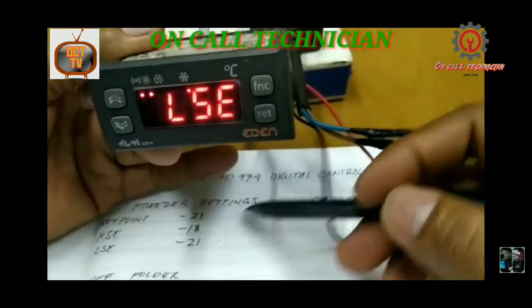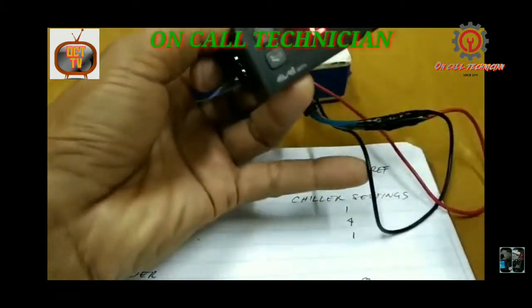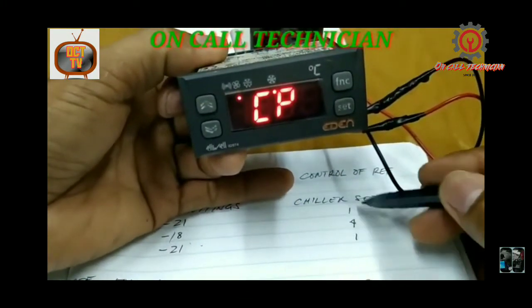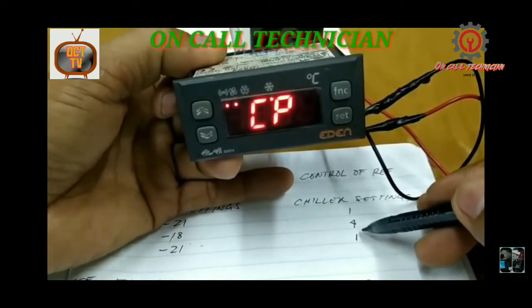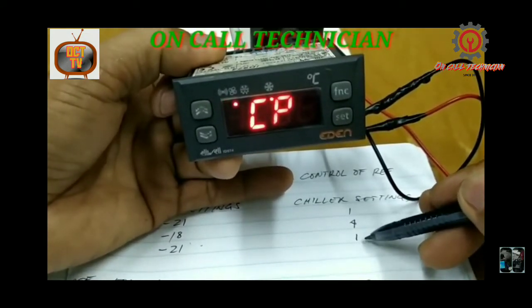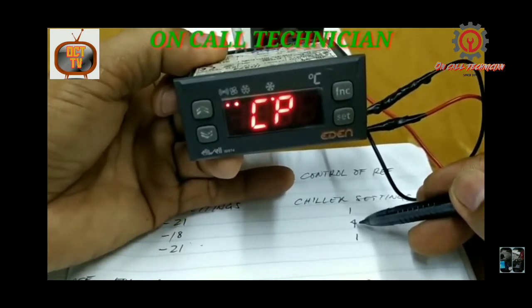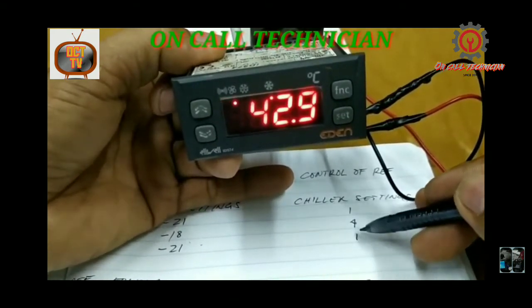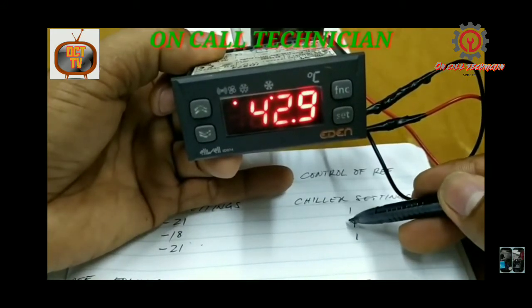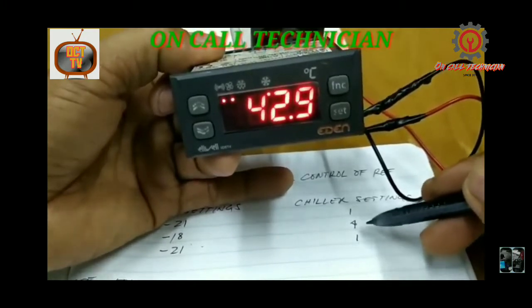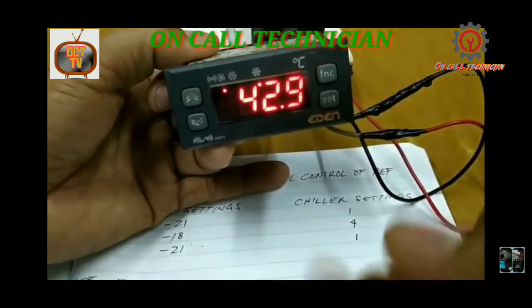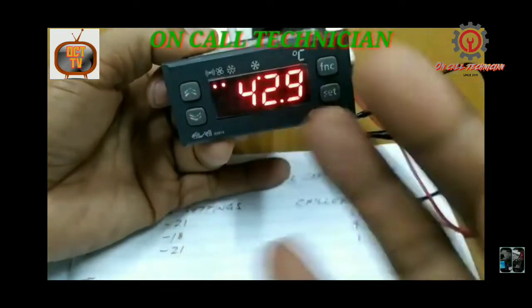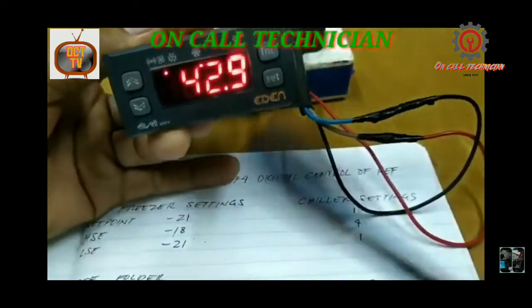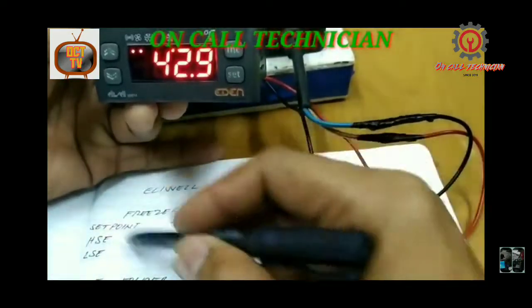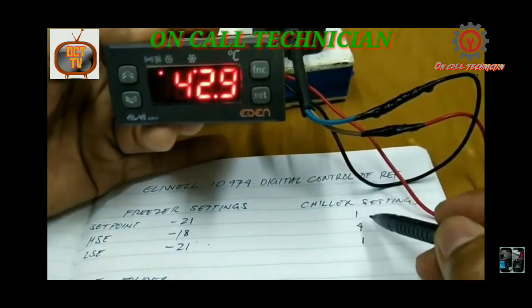The differential I put in is 3. So the compressor starts at 4 degrees Celsius and will stop upon reaching +1 degree Celsius. That is the operation of our compressor, guys. The compressor starts at 4 degrees Celsius and cuts off at 1 degree Celsius, so we have a differential of 3. This is the freezer setting and this is the chiller setting.